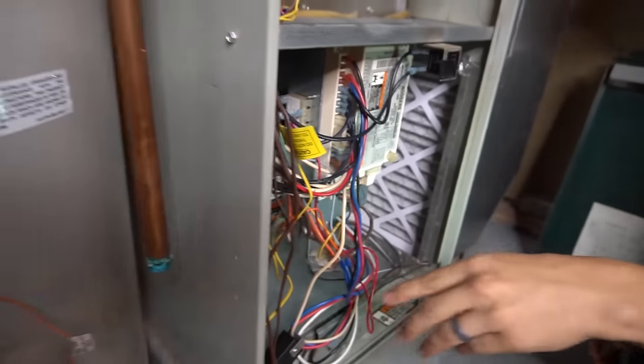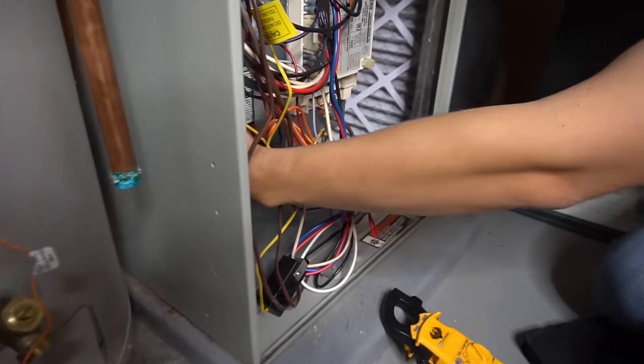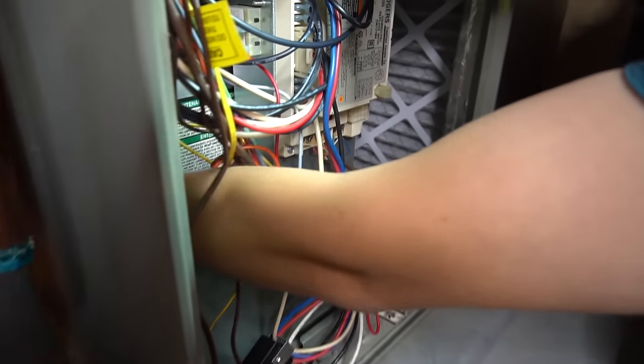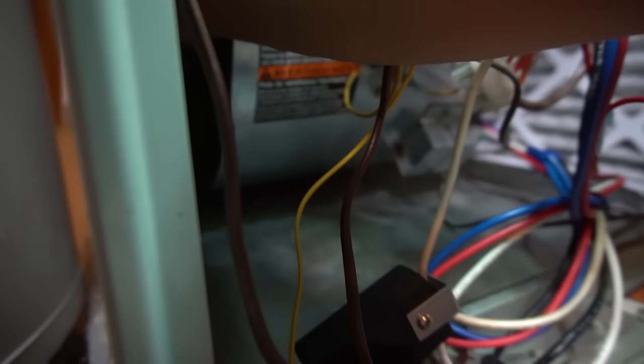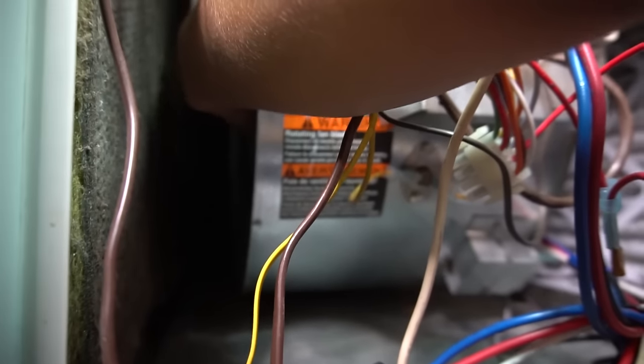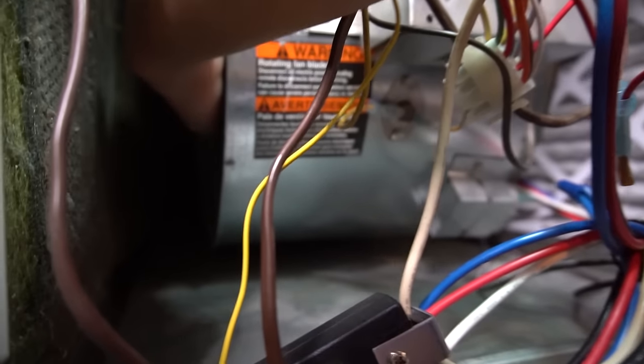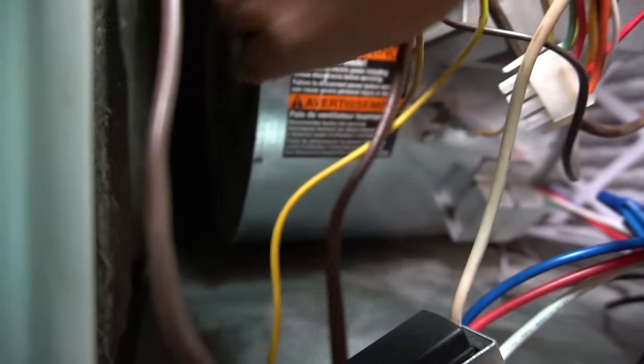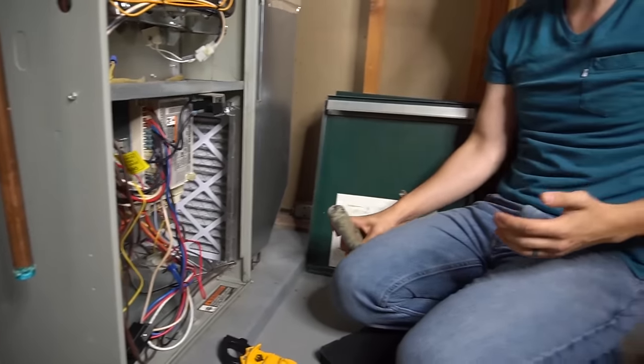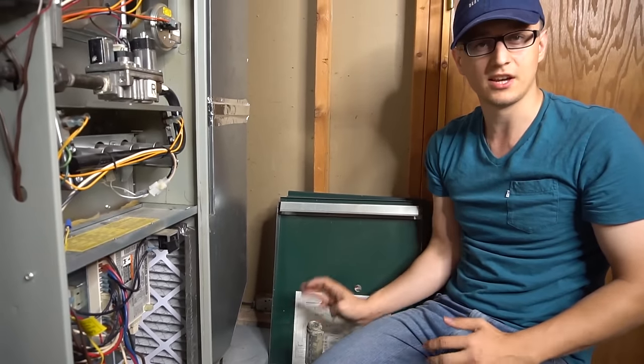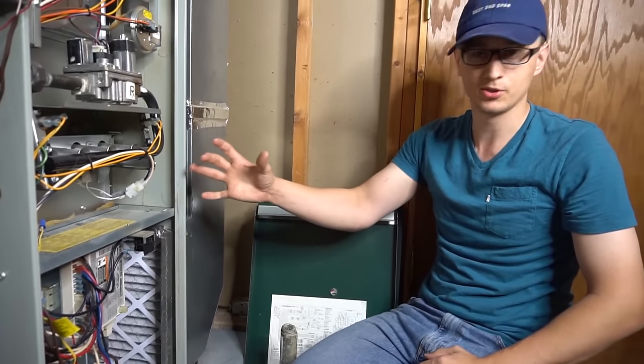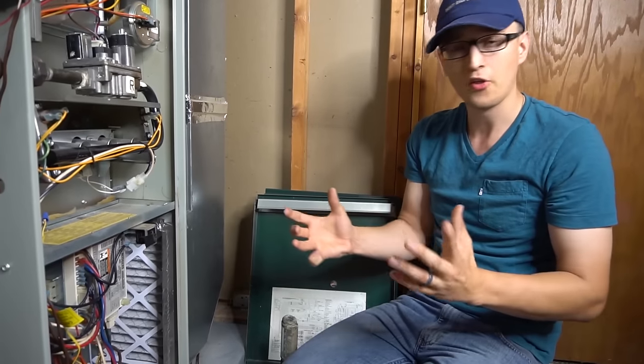Also, if you go on the left side and feel the squirrel cage, a lot of times it'll not spin very freely. It'll feel kind of sluggish and seized up. Just try to spin that by hand. Be careful though, because the fins can be sharp. Those are pretty much obvious giveaways that your motor is bad, if that motor is super hot.